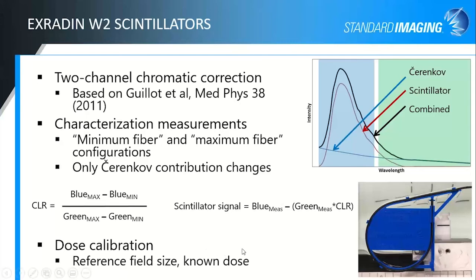You can give it a dose calibration. This isn't necessary for scanning measurements that are all relative, but you can tie the output to a known dose if you give it a dose with a reference field size. These little tabs here on the bracket do mark the active point of measurement of the W2 1x1 fiber. So you could center your field there for your dose calibration measurements.